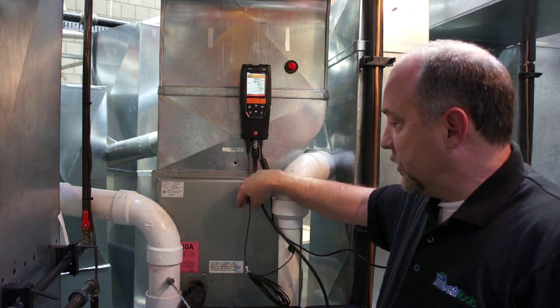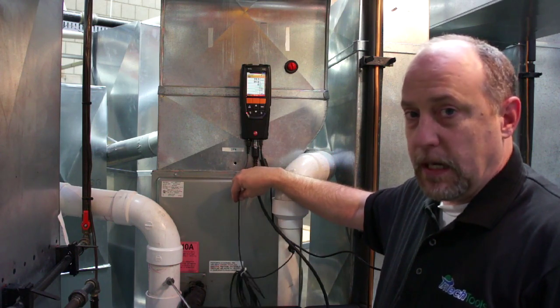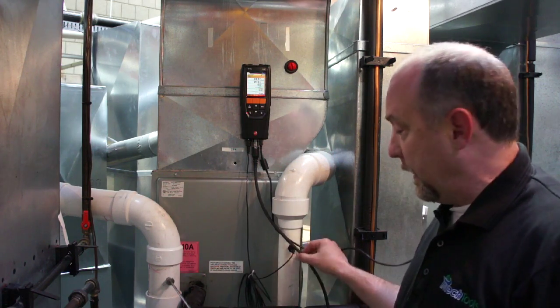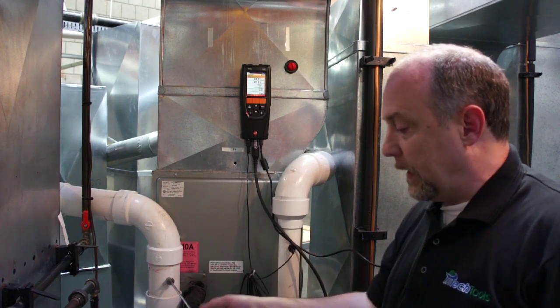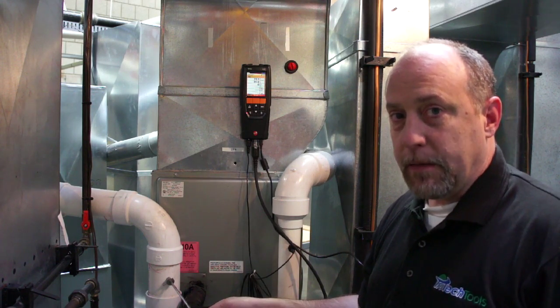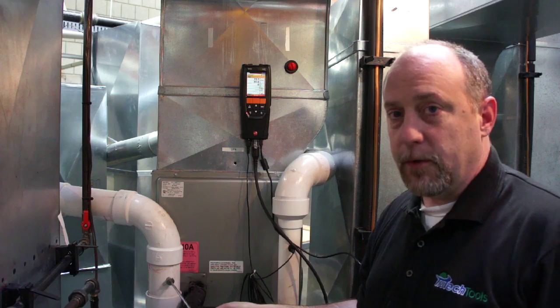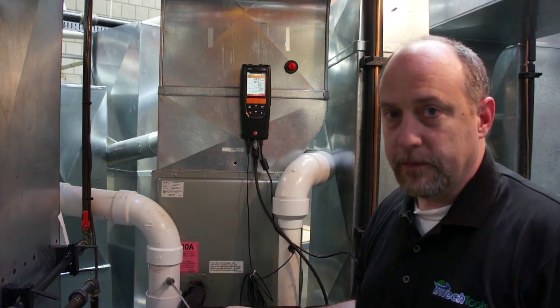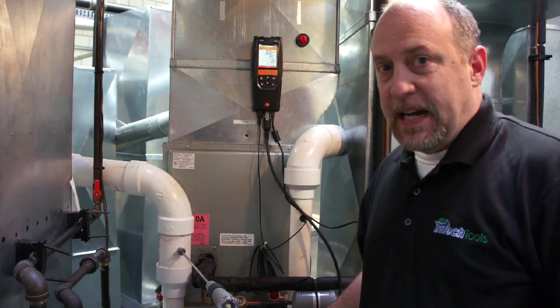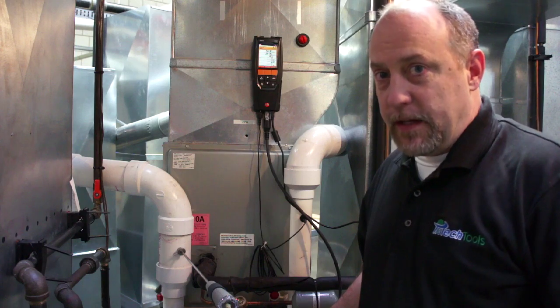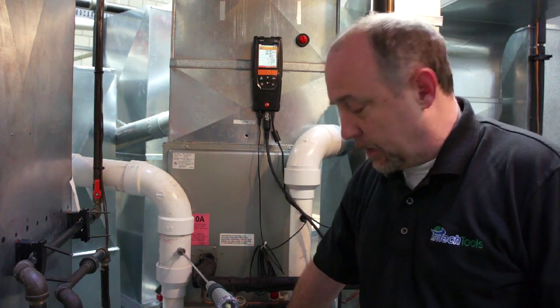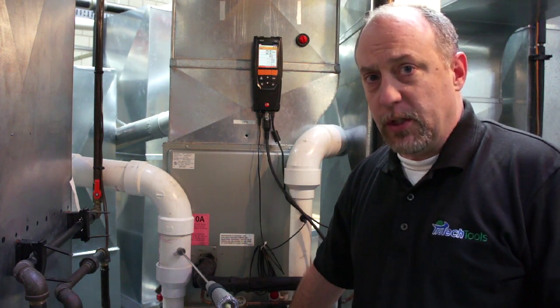So now I've got the analyzer set up, I've got my combustion air probe set up, I drilled a small hole in my flue pipe here, I have that probe mounted in the flue pipe, and I have my stack gas set up. I'm going to go ahead and start the furnace up, let it run for a few minutes, then we're going to start a combustion test. Because this is a 90 plus, again, I can't stress enough that you have to have the bottom combustion door on the furnace when you're doing testing.